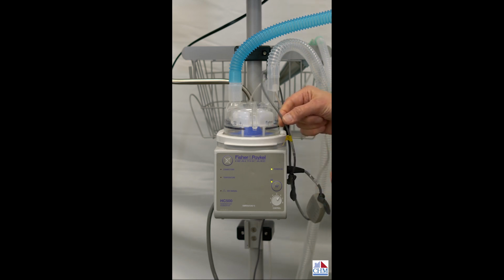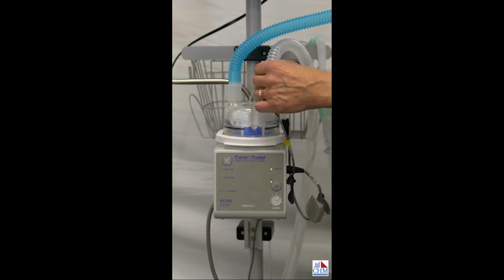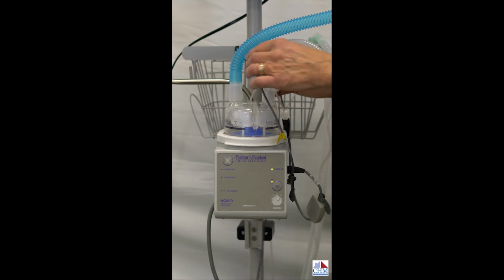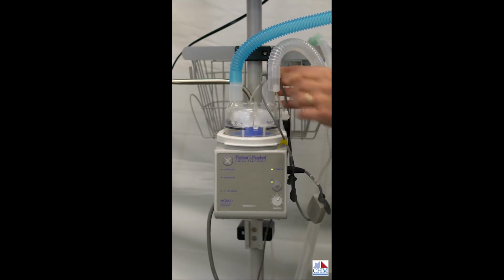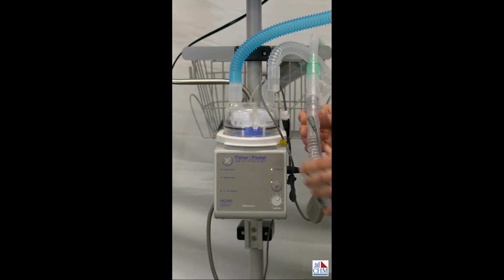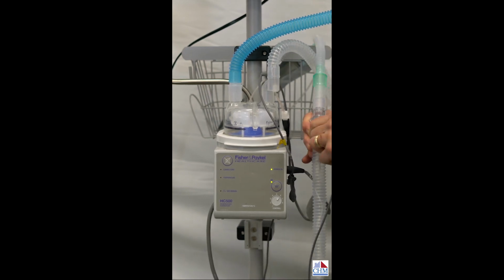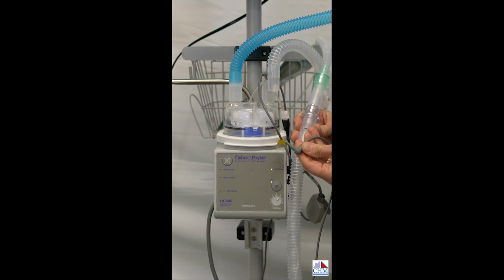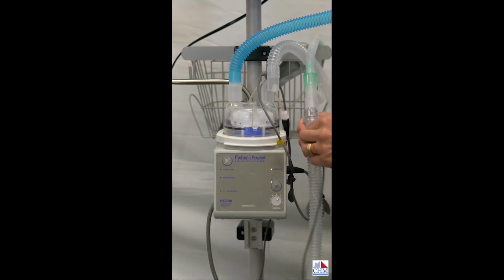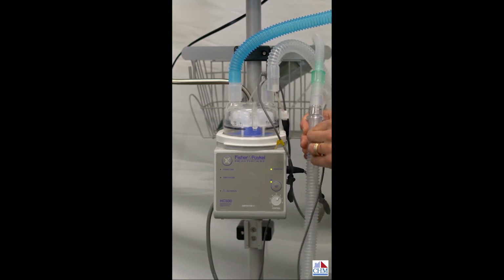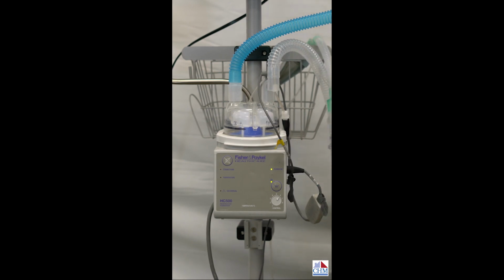The most common problem is this heated wire adapter. Now, I'm sorry, this is the temperature probe. The temperature probe runs from the side of the machine, and then it has a sensor right here, and then it has another sensor all the way at the end of the circuit here, proximal to the patient. So these are involved in sensing the temperature, and it acts as a thermostat to turn on and off the heater to maintain the proper temperature. So the easiest thing to do, if we suspect, and usually we'll start with this one because this is the most common problem, is to start by exchanging it.